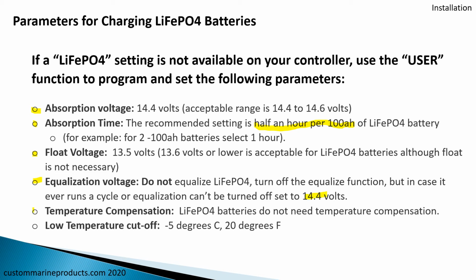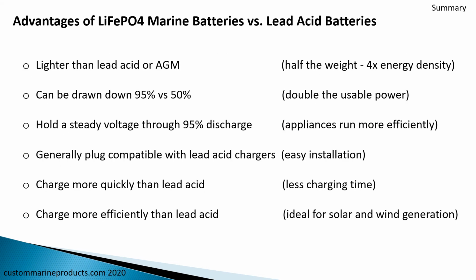Temperature compensation with these batteries is not needed because they do not heat up as they're being charged. So the temperature compensation sensors just aren't necessary. And if you have a temperature cutoff on your charger, about -5 degrees Fahrenheit or centigrade, or 20 degrees Fahrenheit is a good cutoff temperature for full charge. So these are some of the settings you want to do.